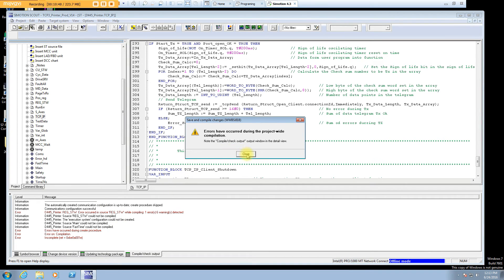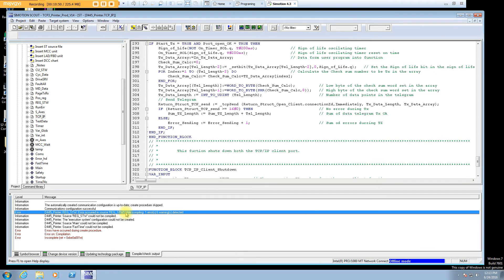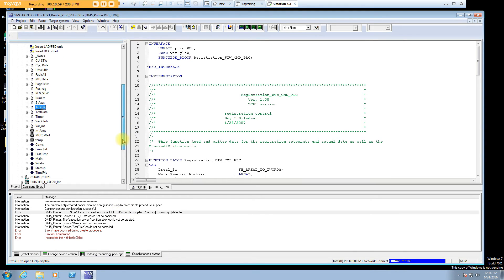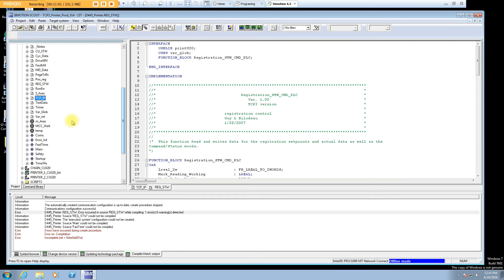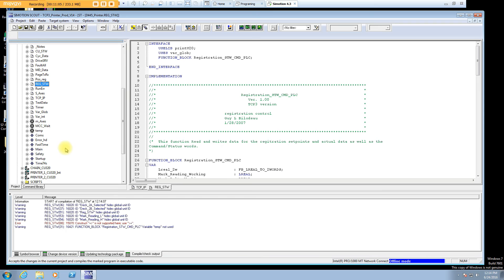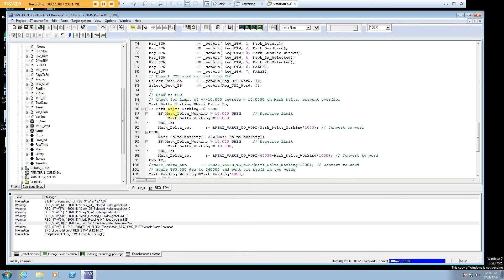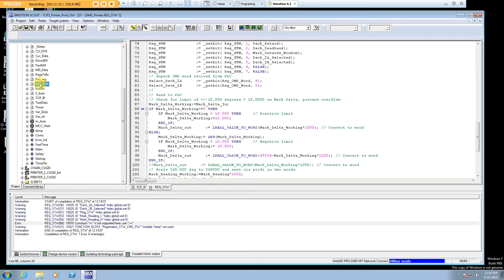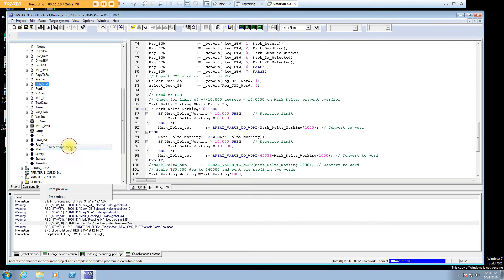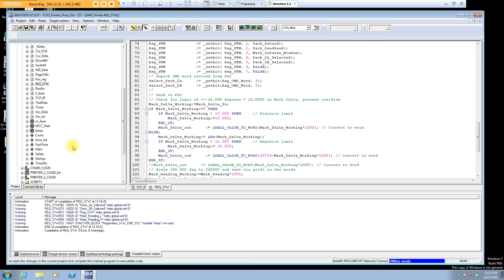Now, notice here, when you do the basic compile, it flags a routine, not what's wrong on the routine. You have to go open that routine and do an accept compile on it to tell you which actual lines it's actually upset about. So you kind of have to drill down. There it shows, it brings you right to it by double clicking. Again, it's the same thing. You get another routine that actually didn't get used.